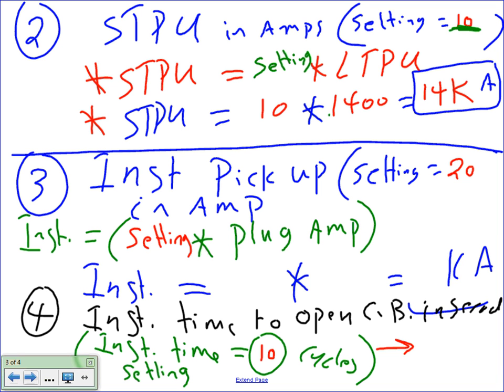Number 3, guys, I need instantaneous pickup. I'm setting it at 20, and I need you to find the instantaneous pickup in amps. That's if all hell breaks loose and I tie the ends of phase A to phase B to phase C and I flip the switch on. That's the largest amount of current that this circuit breaker will be able to encounter. So essentially, the bigger the setting, the more it can handle.